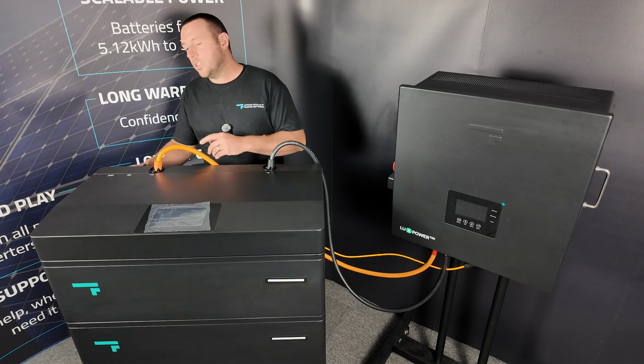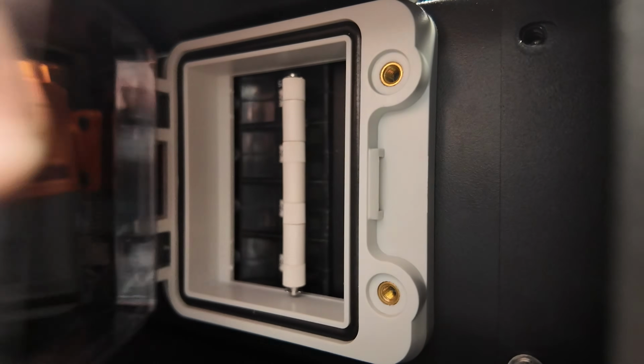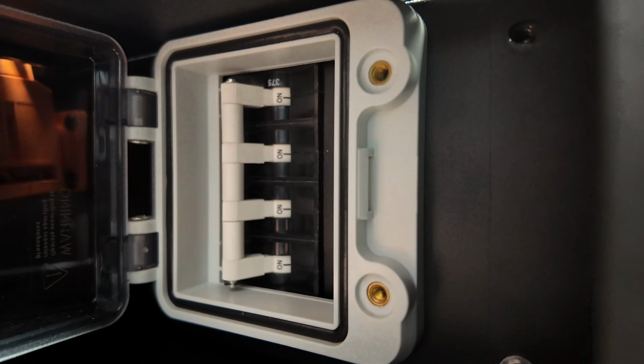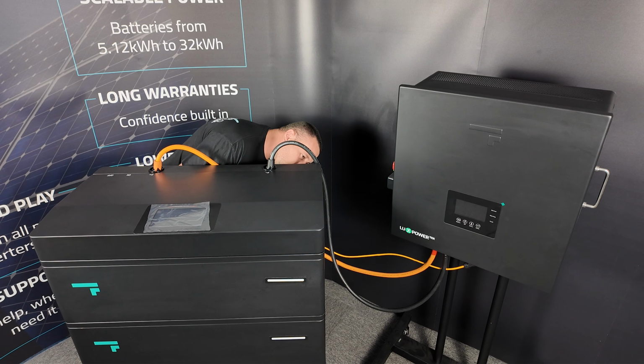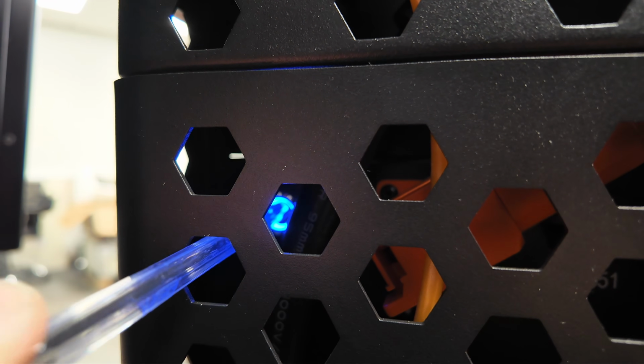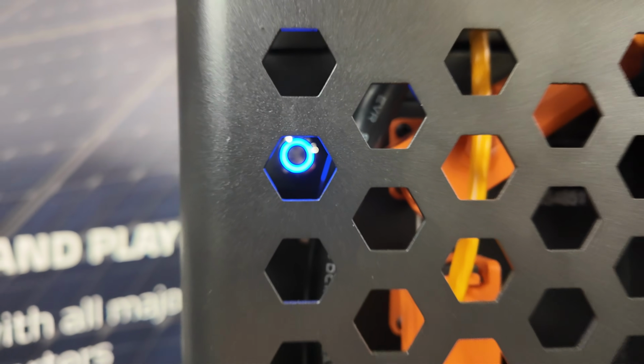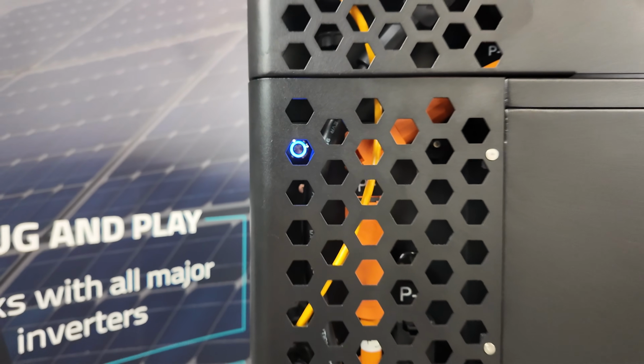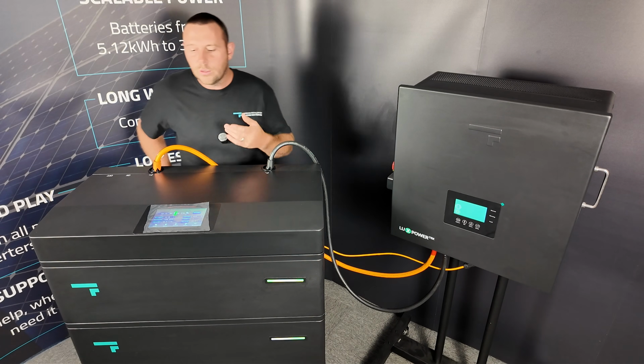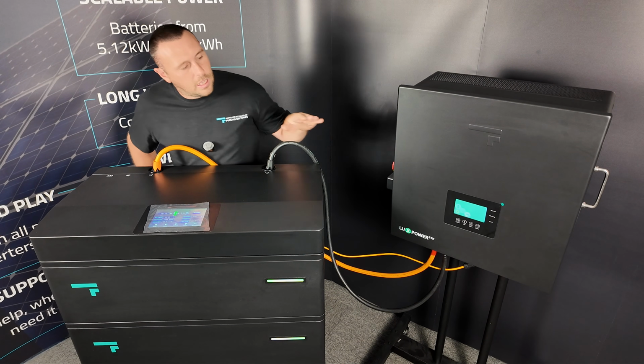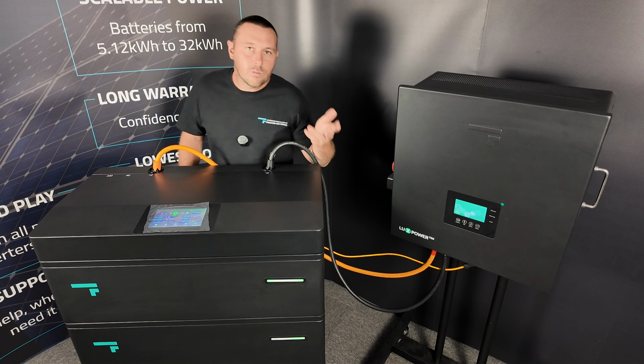Do that by switching on the breaker first. Then you'll need to take the back of a ballpoint pen and poke down through to switch on the modules. Turn on the top module first - this will determine it to be the master - and then work your way down the stack, turning on the power buttons at the back. You'll then see that the screen has lit up, and so is our inverter. If the room was a bit darker, you'd also see that the status LED bars are lit up.